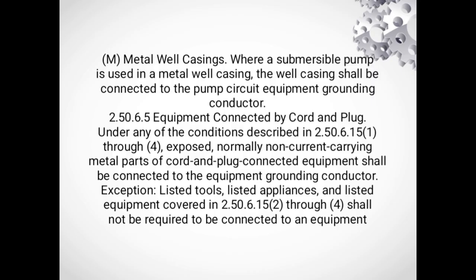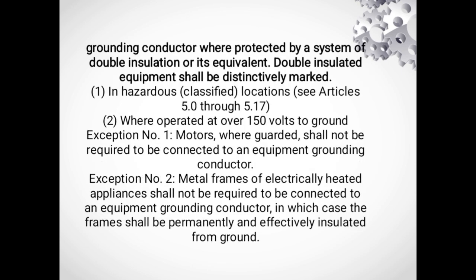2.50.6.5 Equipment connected by cord and plug under any of the conditions described in 2.50.6.15.1 through 4. Normally non-current carrying metal parts of cord and plug connected equipment shall be connected to the equipment grounding conductor, except listed tools, listed appliances, and listed equipment in 2.50.6.15 2 through 4 shall not be required to be connected to an equipment grounding conductor where protected by a system of double insulation or its equivalent. Double insulated equipment shall be distinctly marked.